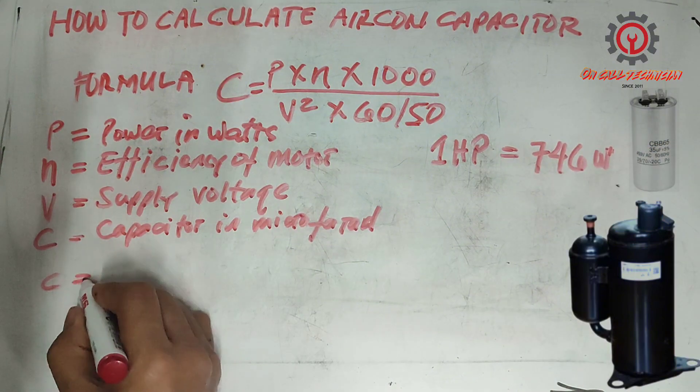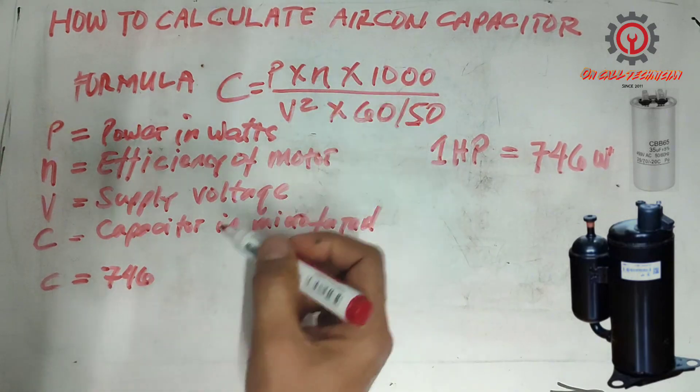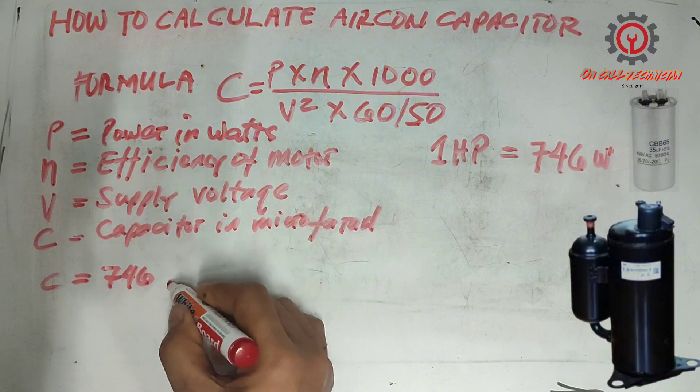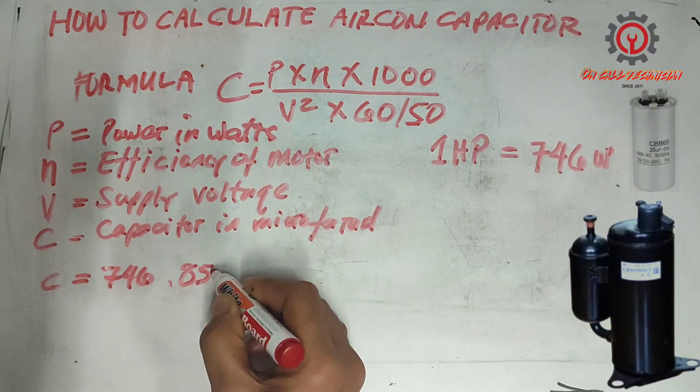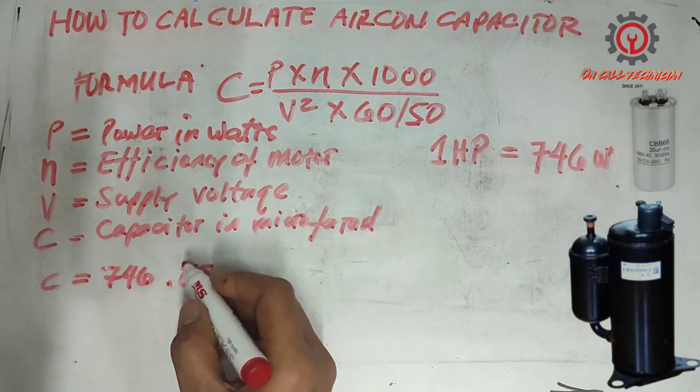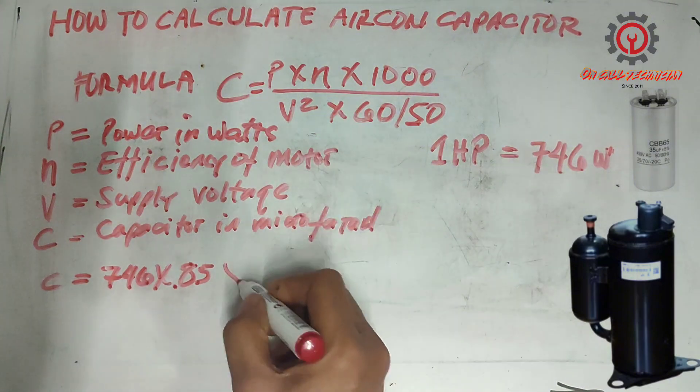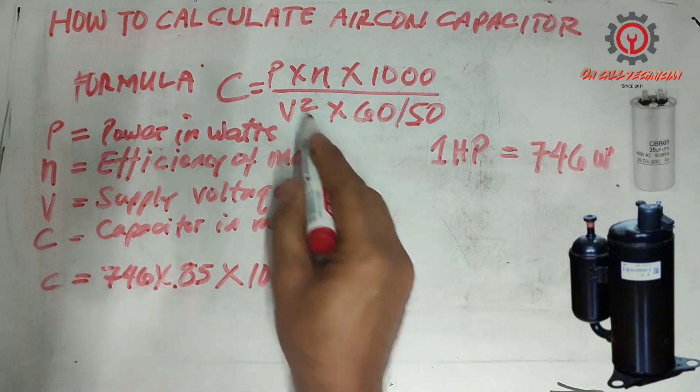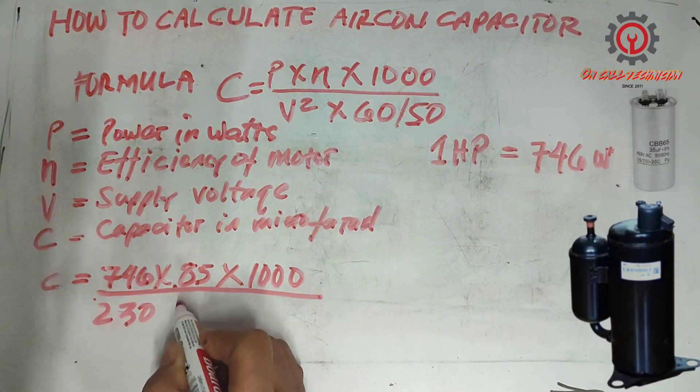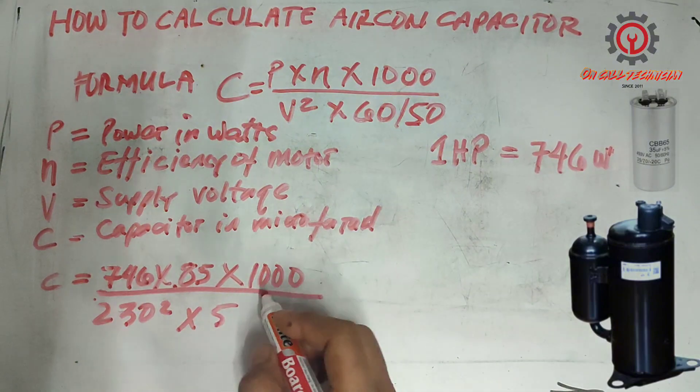C equals 746 watts times efficiency. For example, if the efficiency of the motor is 0.85, or if your efficiency is 90% use 0.9. So 746 times 0.85 times 1000 divided by 230 squared times 60.